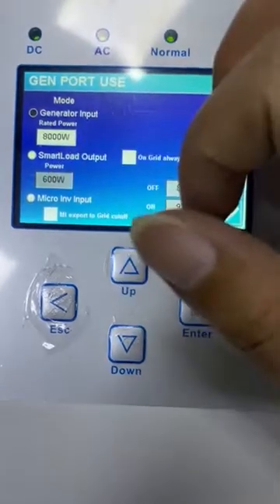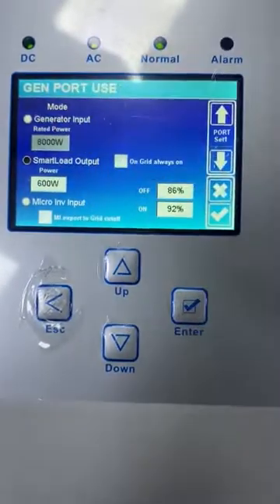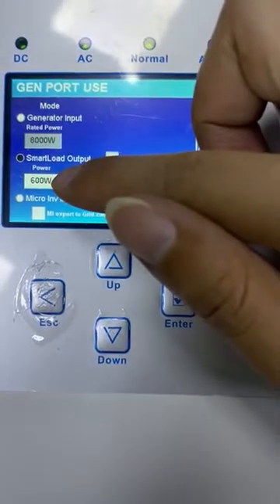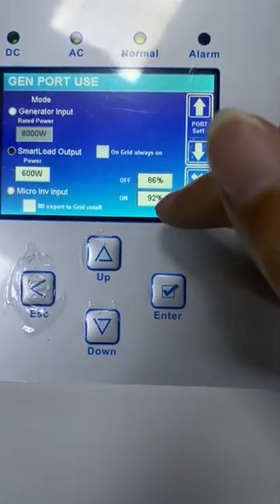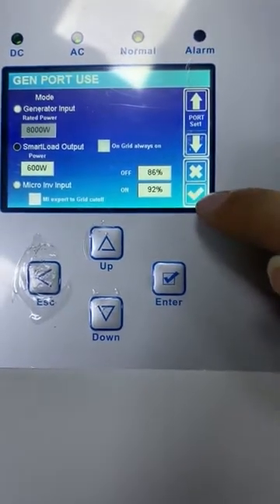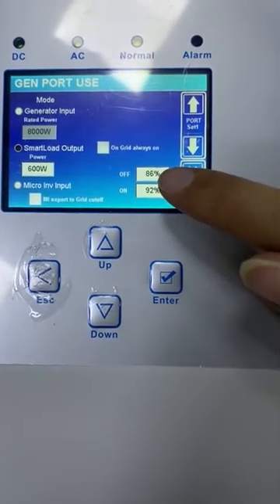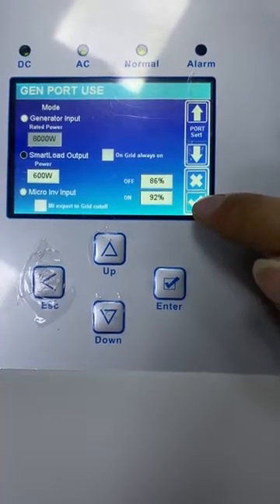As we can see, if we choose the smart load output, it means when the PV input power exceeds 600 watts and when the battery SOC exceeds 92%, it will turn on the smart load. And when the SOC decreases to 86%, it will turn off.